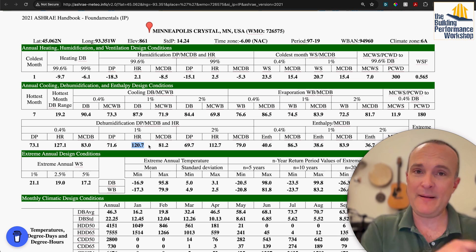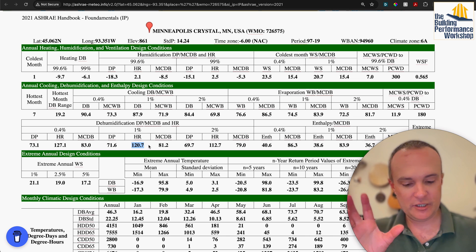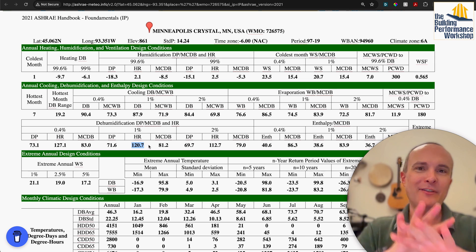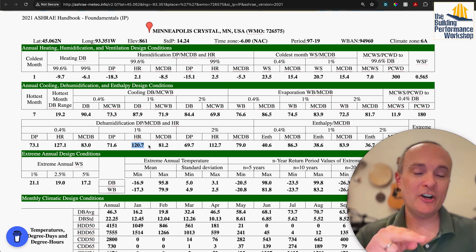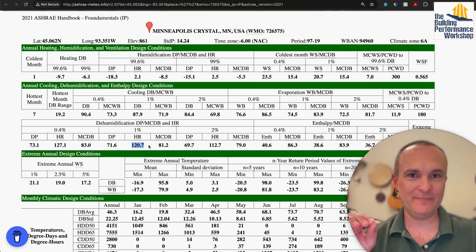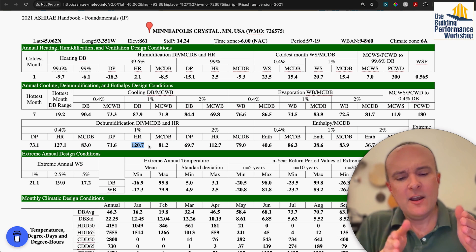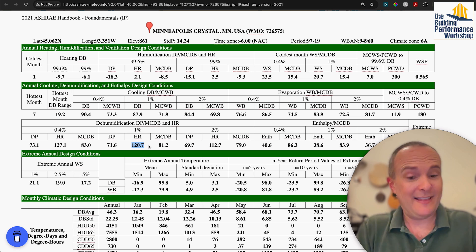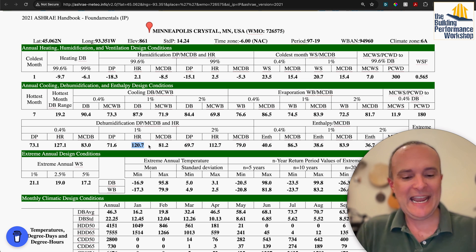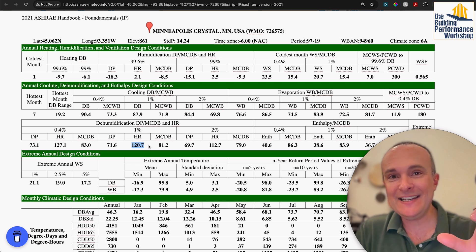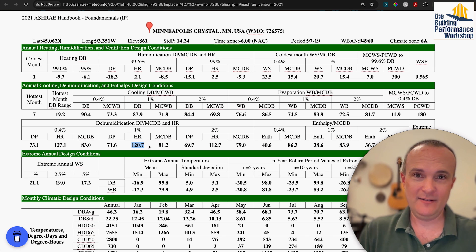To calculate the load, I multiply 55.7 by the 148 CFM coming into the house, then multiply by the coefficient 0.0148 — a magic number that combines a bunch of factors. That gives me 122 pints per day of dehumidification needed. That doesn't mean a 120-pint-per-day dehumidifier — that rating only applies at 80°F and 60% relative humidity. What I actually need is more like a 150 to 200 pint-per-day dehumidifier.